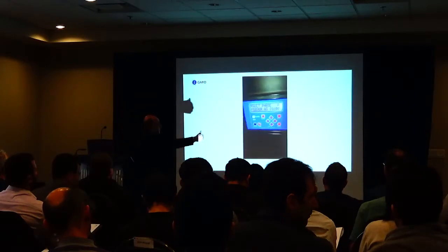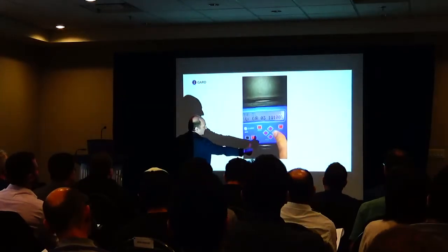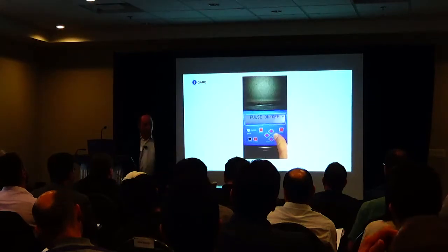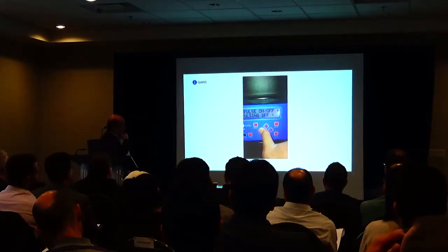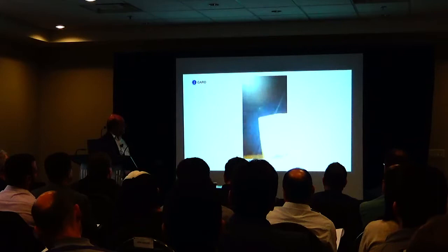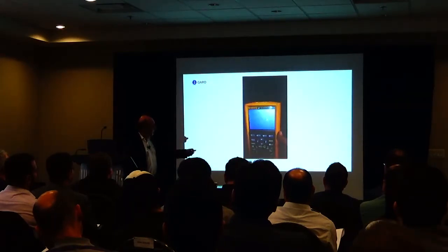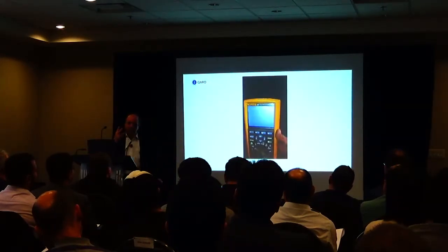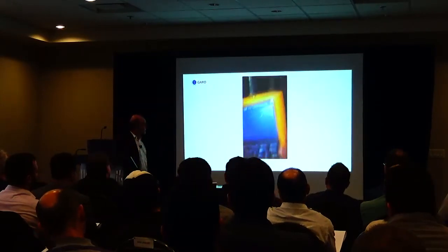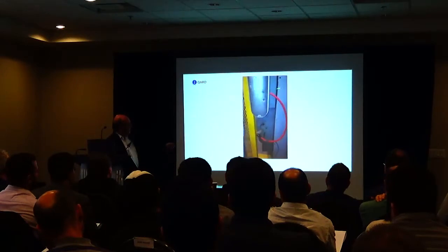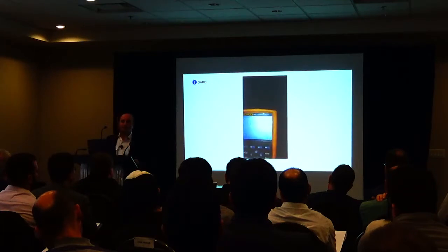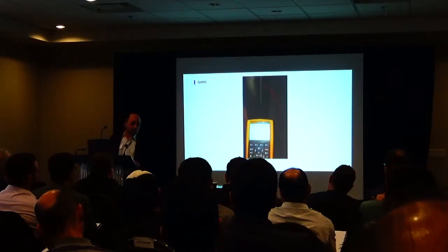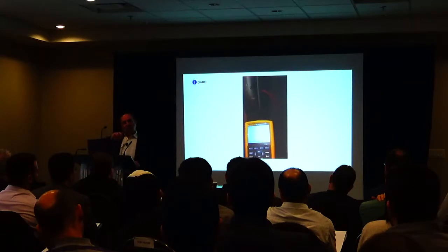So this is our GARD system. I'm going to turn on the pulsing. I don't know if you guys can recognize my thumb. So it's hard to tell, but concentrate on that bar graph at the bottom. If you try to look at the numbers themselves, you're going to go nuts, because digital numbers change so fast. So right around conduit, zero sequence CT, right around conduit. So now you can find the fault without opening up any doors, because what you're looking for is the pulsing.